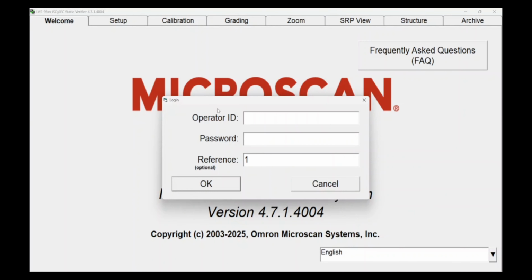We will first log in using either your user ID or password, or you can use admin. Head to the calibration tab, and there are written instructions here if needed, but make sure to take your conformance calibration card out of the plastic sleeve and make sure it is not expired. These cards must be replaced after 2 years of use, and there should be a date of expiration in the bottom corner of your card.